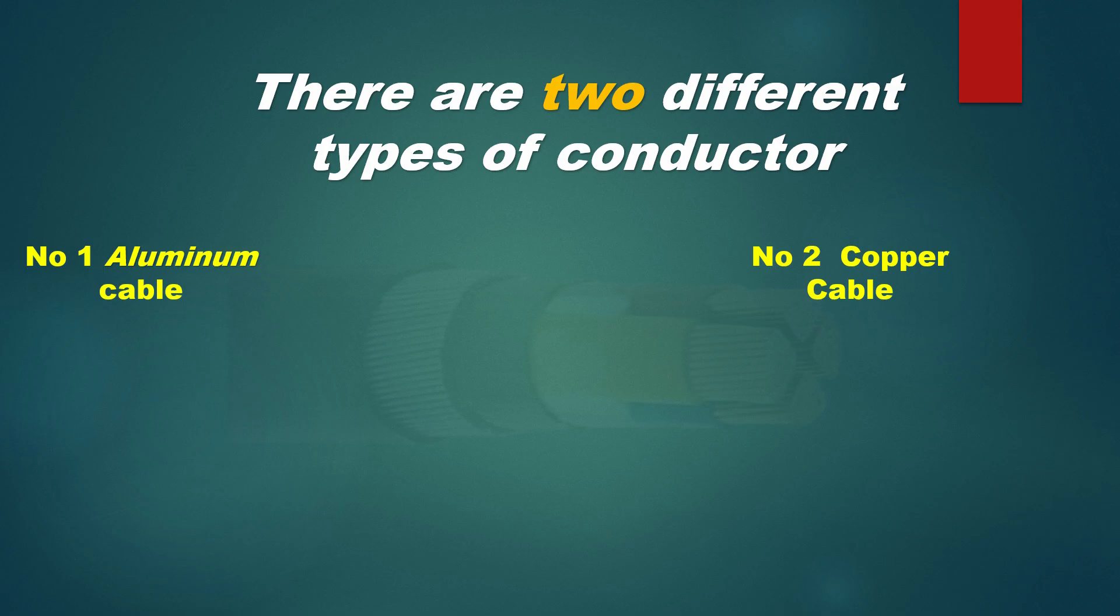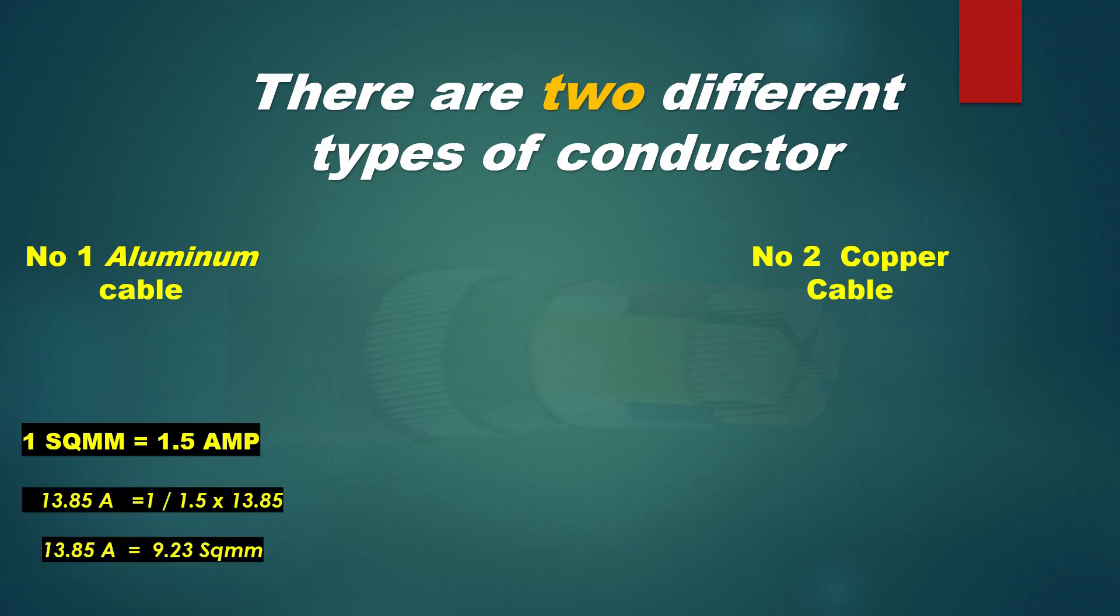According to the thumb rule, per Aluminum cable is 1 square mm, cable carrying capacity is 1.5 ampere. So, the cable size for 13.85 ampere is equal to 1 divided by 1.5 multiplied by 13.85. The answer becomes 9.23 square mm. As it is, according to the thumb rule, for copper cable carrying capacity is 1 square mm is equal to 2.5 ampere.